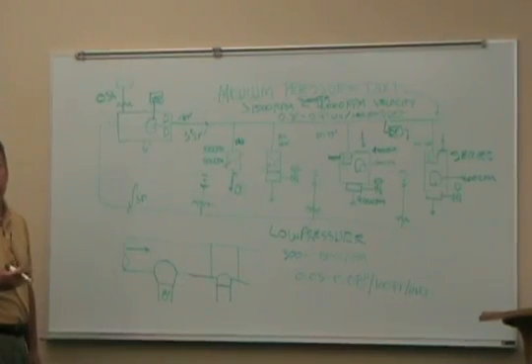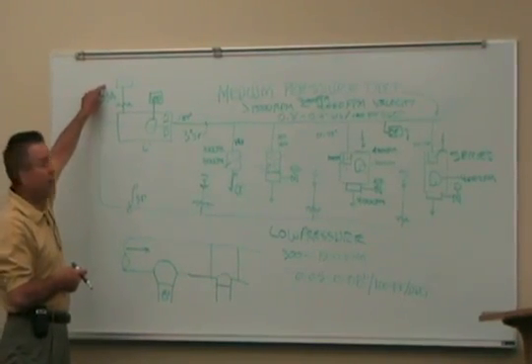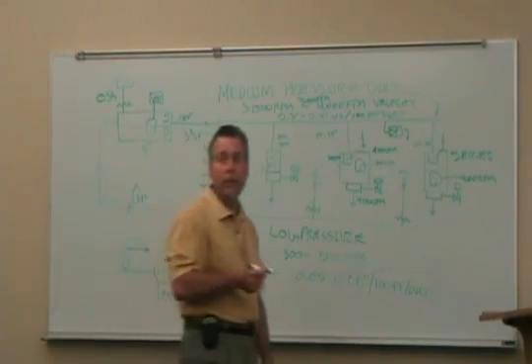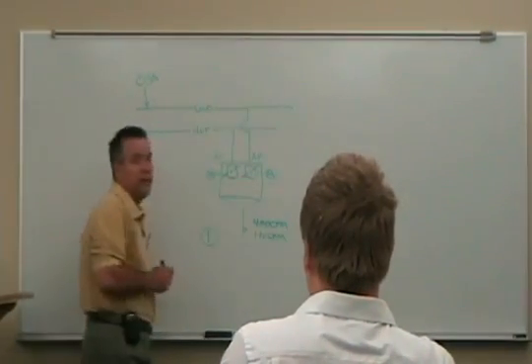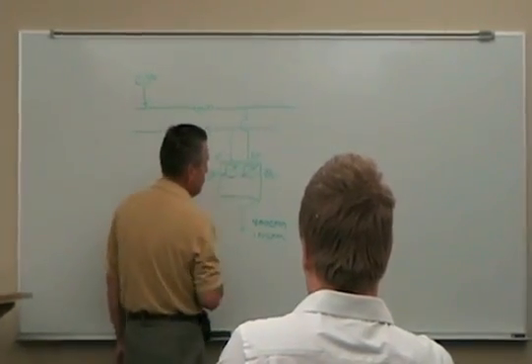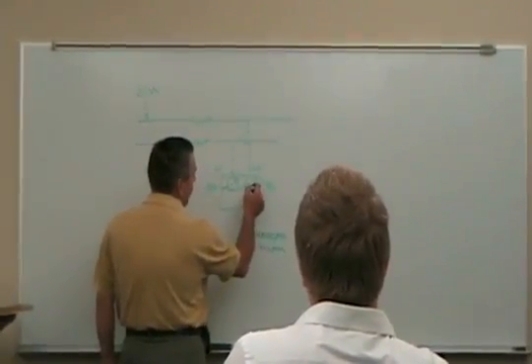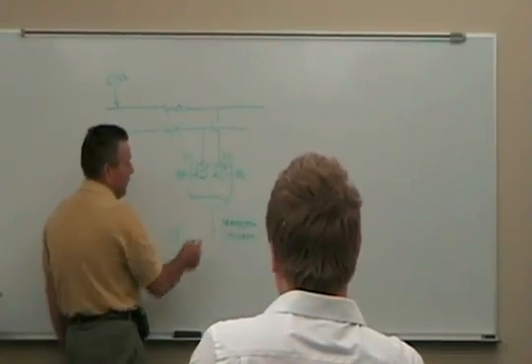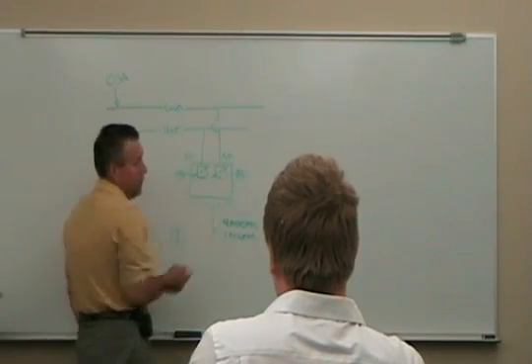What does a cooling coil do? It dehumidifies. So in the summertime, I've got hot and humid outside air. I've always got to make sure it goes across the cooling coil to get it dehumidified. So generally, your cold box is going to be the minimum airflow. This is always going to remain closed until I need heating. So what happens when I need heating, this box closes to its minimum position of 100 CFM. This airflow makes up the difference to get up to 400 CFM. So that's how a dual duct box works works.